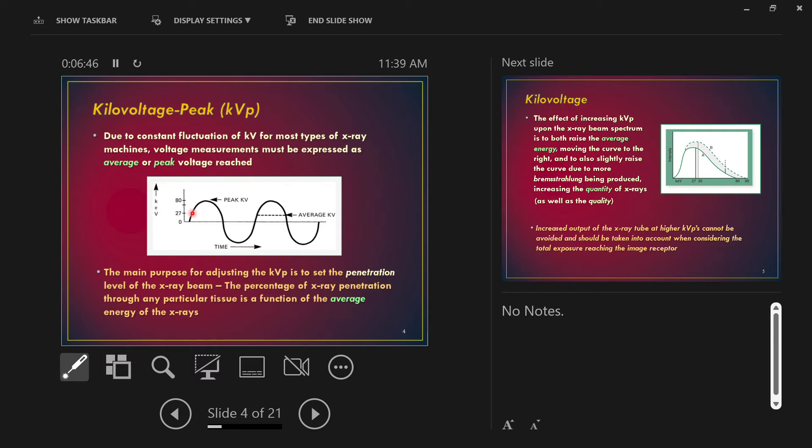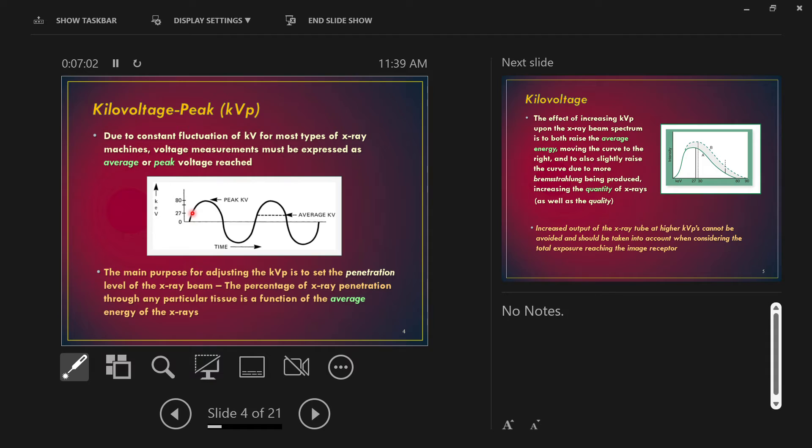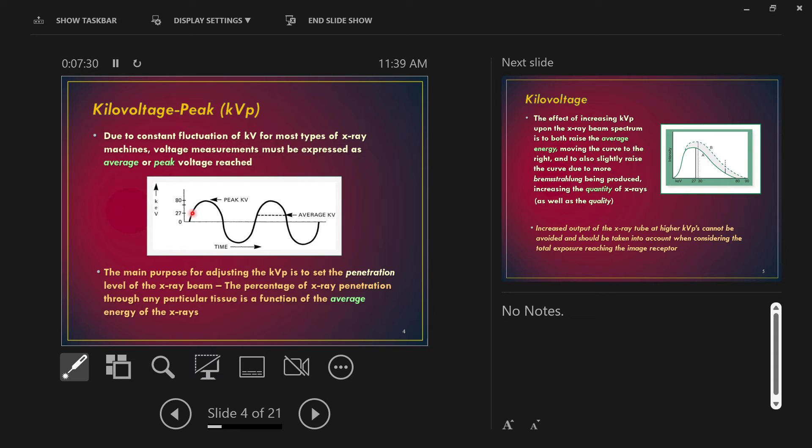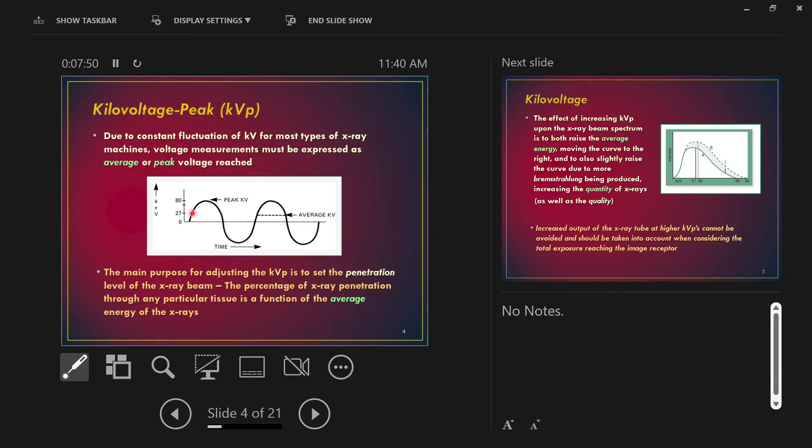Small other side note, depending on your generator, your peak energy and average energy can actually get very close together and almost be identical. If you remember from the talk about generators, the high-frequency generators, the high-frequency or the multi-phase generators, remember three-phase, six-pulse, those ideas - those different types of generators will give an average energy that is much, much closer to the peak energy. For example, in a three-phase six-pulse, I think it's like 91 or 93% of the peak energy is your average. So if your peak is 100, then your average is like 91 KV. Your peak and average get closer together with more efficient generators. On a machine like we have in our X-ray room, what's called a single-phase generator, single-phase full-wave generator, you get beam energies that on average are only about a third of what you set. So that's something to keep in mind.